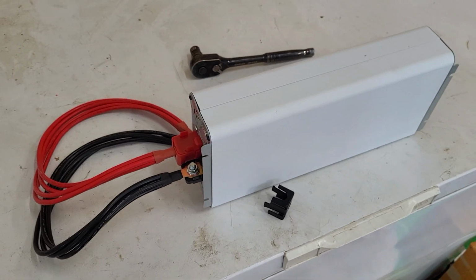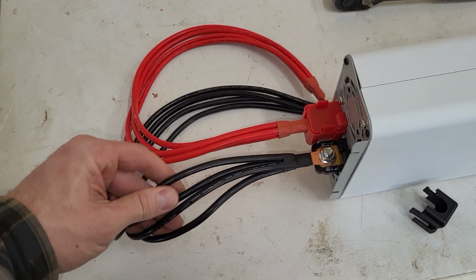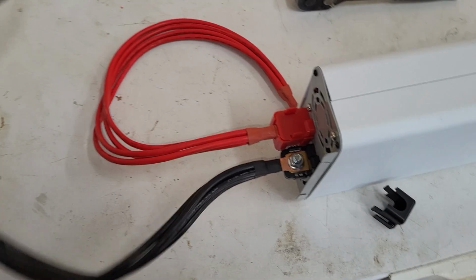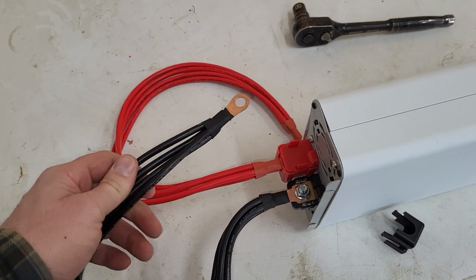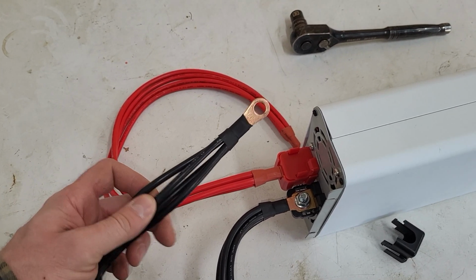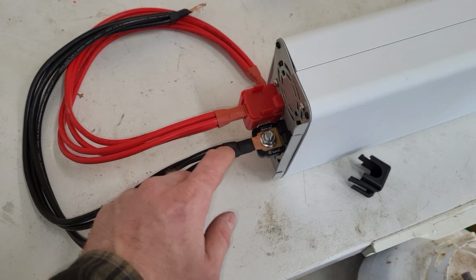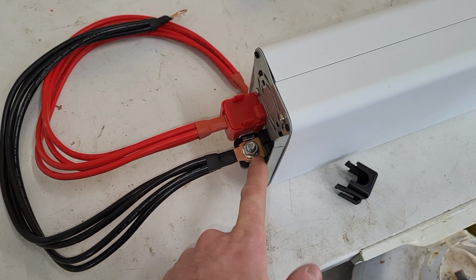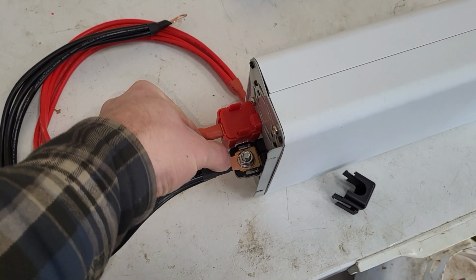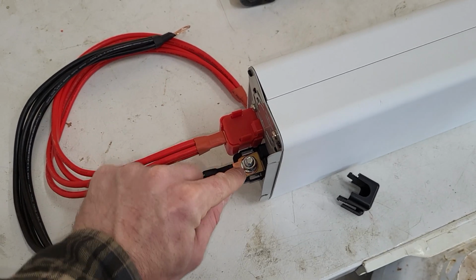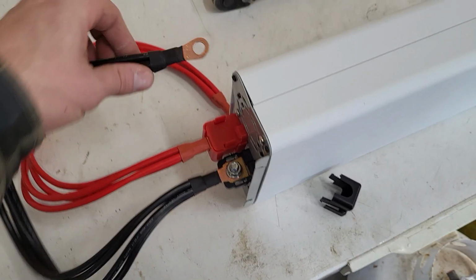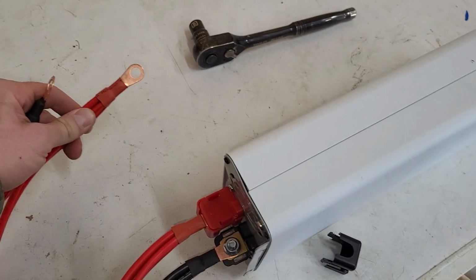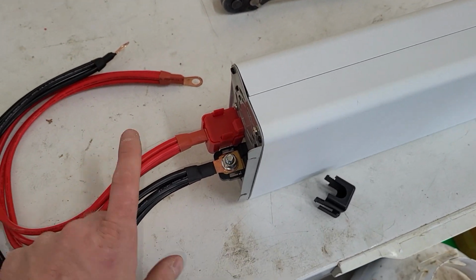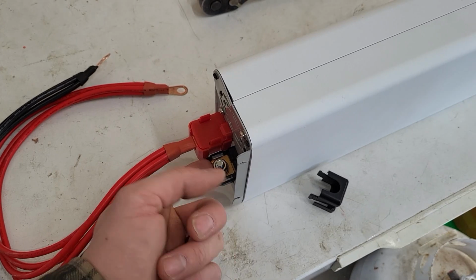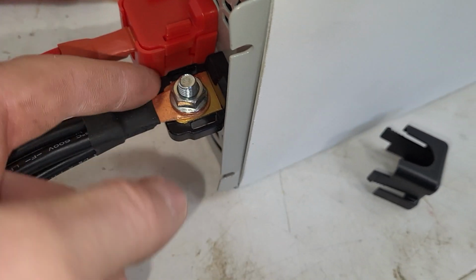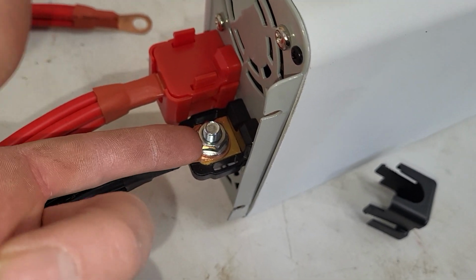The last little bit I'd like to add: I know some people don't like the multi-strand wires, I don't really care, it's all the same, as long as there's the same amount of wire in all these, it'll conduct the same. But what I really like is they do their heat shrink nicely. They don't overlap and go underneath into your ring terminal area, like that on both sides. That's something a lot of people don't catch, and if that goes underneath your nut here, that can give you a bad connection, give you problems.